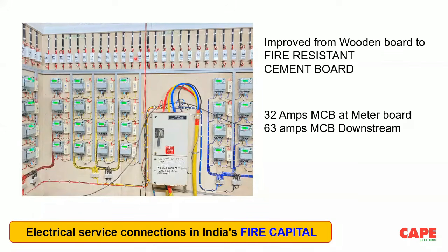So imagine a situation after a few years, due to some reason, you bypass this 32 amp MCB. Until the 32 amp MCB works, it's fine. But if you bypass it under any condition, or if it is not working, then the chance of fire in this installation is quite normal. It can catch fire. So this is actually a small thing. The builder, instead of 63, could have given a 32 amp MCB.